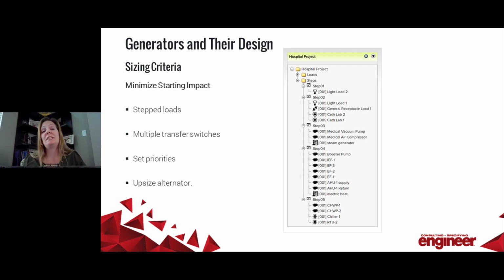One way to minimize the impact on the generator is to bring loads on at different times. This is referred to as stepped loads, and it allows you to connect only a portion of the loads at a time, wait for the system to stabilize, and then bring more loads online as the system permits. This allows you to make the blocks of loads smaller, therefore having a lower impact on the voltage drop that creates transients on the EPSS. This is what makes those generator sizing software programs so handy, because you can play around with the step loads. You can set the appropriate priorities, play with the order in which you want to connect them, and truly assess the loads to ensure that the generator is sized to handle the transients, which again may mean upsizing the alternator. Have I said that yet?